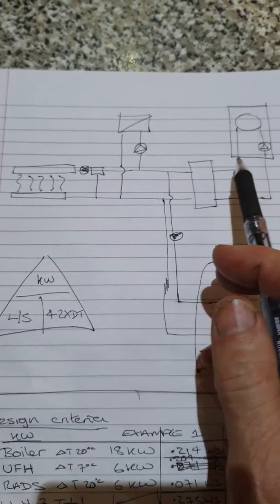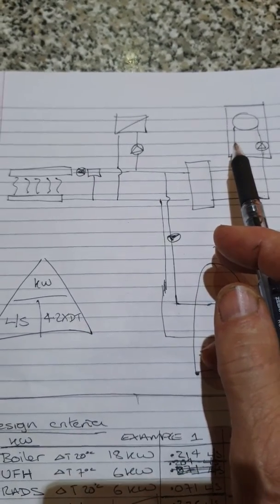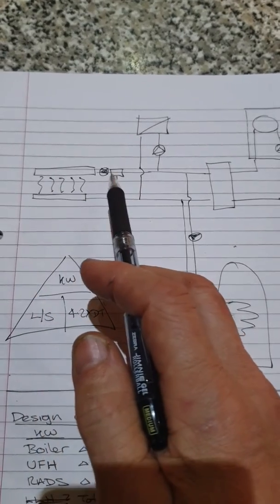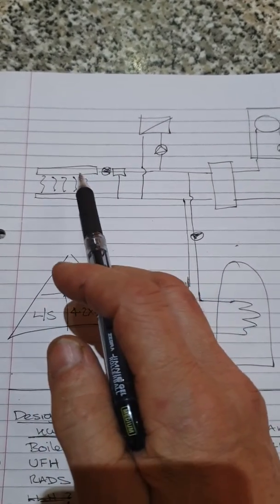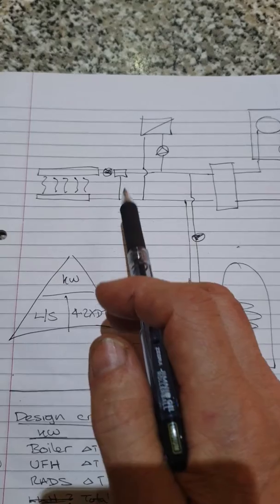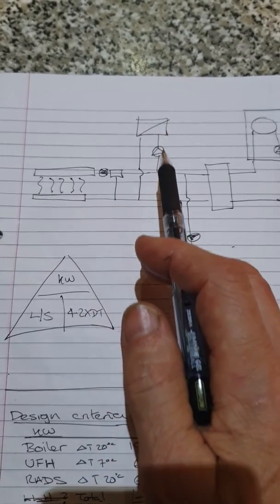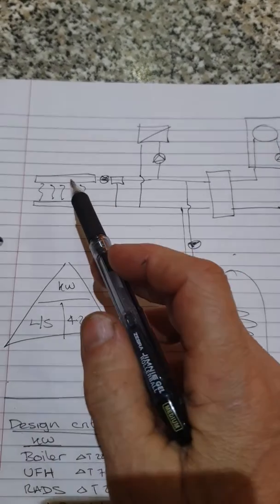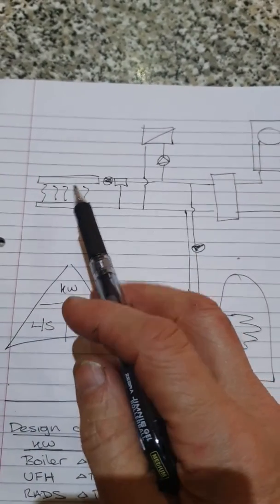But if you go to the boiler and turn this temperature right up, you start to deliver enough water here for the blending valve to kick in and start shutting down, allowing the flow to be diverted off to the radiators. Also, because you've got over-temperature water, the recovery rate for the underfloor heating is higher.